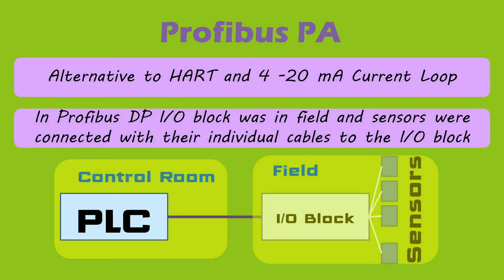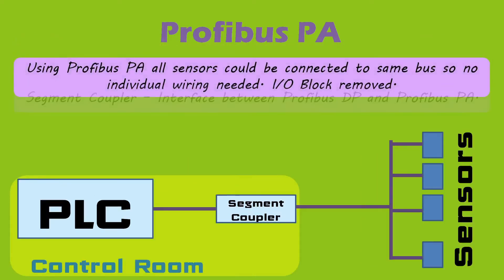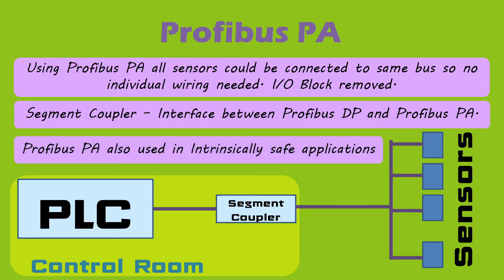Profibus PA stands for Process Automation. It was designed as an alternative to HART or 4–20 mA current loop communication. While Profibus DP carried the IO block to the field with individual sensor wiring, Profibus PA simplified this further by connecting all sensors to a single bus in the field, removing the IO block and individual wiring. An additional element called the segment coupler is introduced, which acts as an interface between Profibus DP and Profibus PA. Profibus PA is also used in intrinsically safe applications.